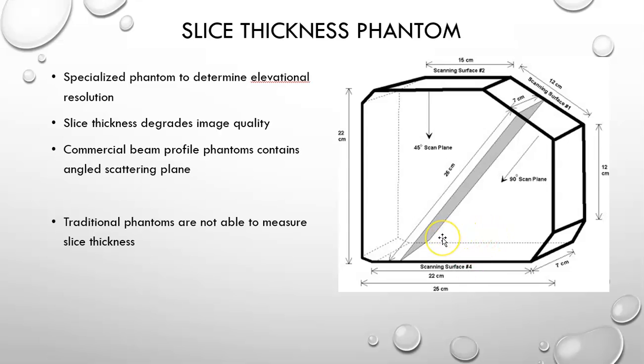And as it says here, traditional phantoms are not able to measure slice thickness. Well, yeah, that's absolutely true. Anyhow, you measure it exactly like we did in the lab. You measure across the 45 degree angle, and the measurement from top to bottom is what provides you with the thickness of the slice.